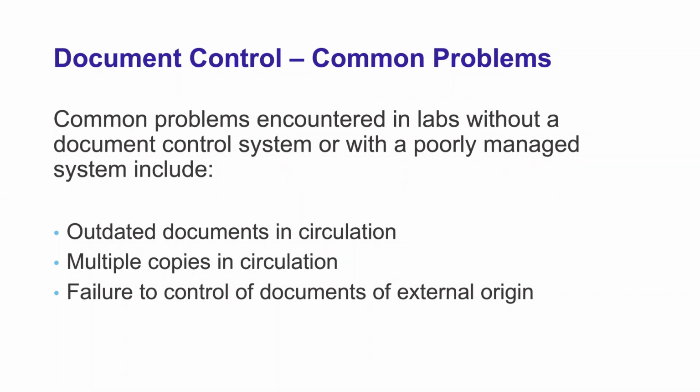And failure to control copies of external origin. These are, again, those manuals, the package inserts, the regulations. If you don't have a way of cataloging and controlling those, they can get lost or just be filed in a random drawer somewhere, or maybe you have someone at the bench who's using the package insert instead of the SOP. So you need to make sure you're not only controlling the documents you created, but the documents that you've accepted into your laboratory that you use to inform your SOPs. So that's all for documents.